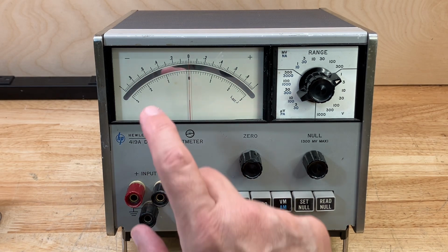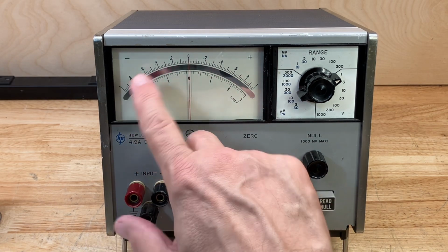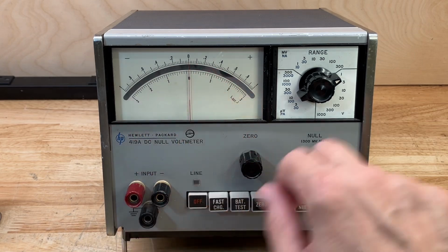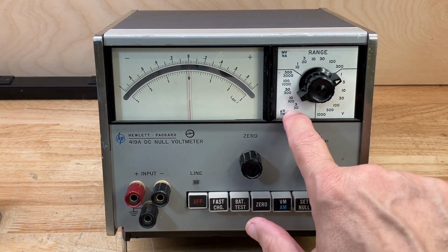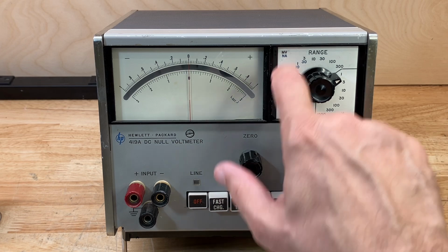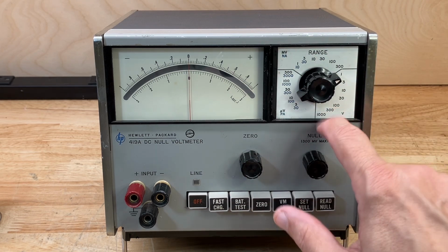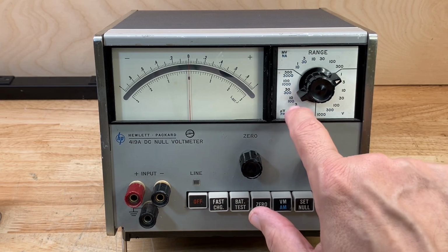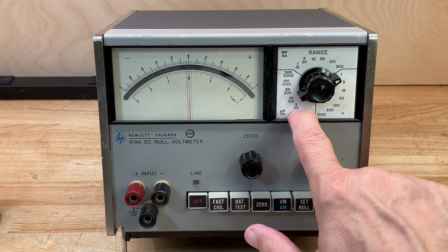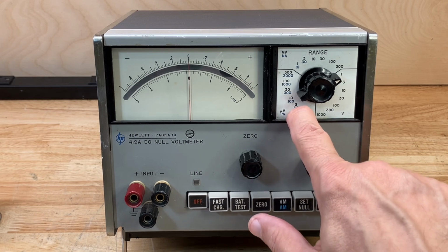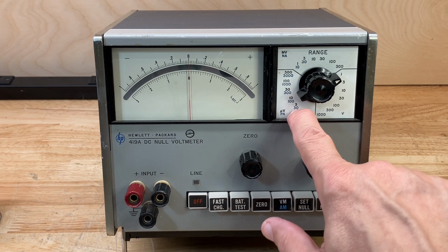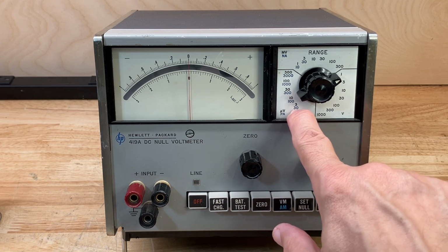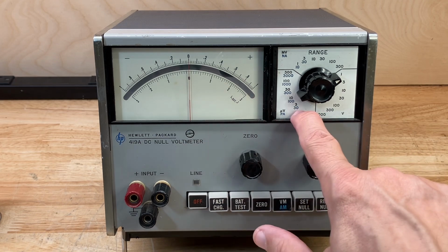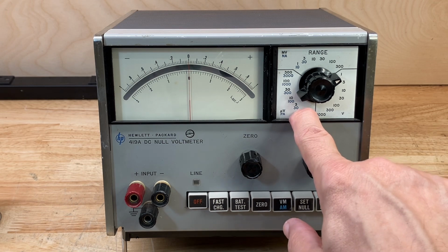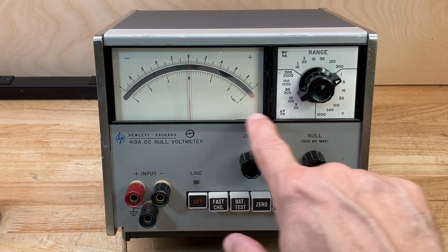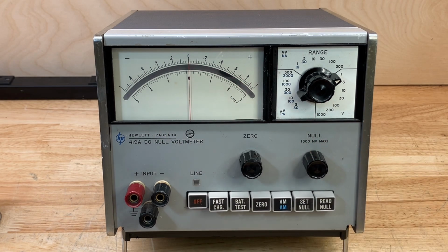On the front panel, of course, we have the mirrored scale meter. We have the range switch with ranges from 3 microvolts all the way up to 1000 volts. The instrument can also be used as a picoammeter with a resolution of 30 picoamps on the lowest scale. It's basically like a galvanometer that they used in the old days — you can measure very, very tiny amounts of current with this instrument.